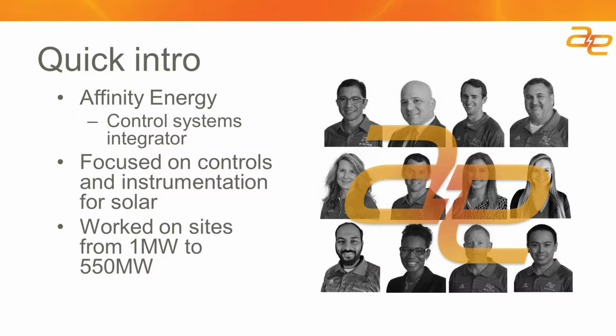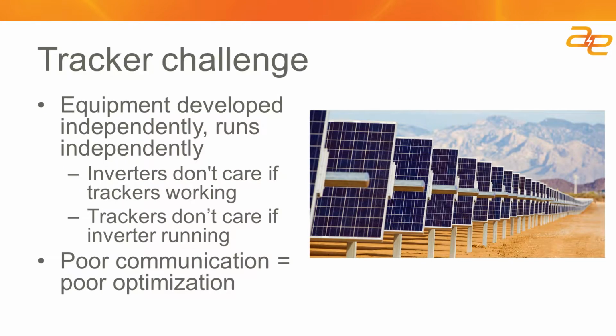So I've seen a lot of different systems, and I've seen things that work well and things that don't work real well. One of the good things is also a bad thing about trackers in general. Trackers, like many solar site components, are designed to operate independent of the control system. It's an island of automation where there's some integration from monitoring, but the tracker system is designed to work independently of whether or not there's a plant control system. The good thing about that is that if there's a communications loss or some event, the tracker will never be in a situation where it doesn't know what to do.